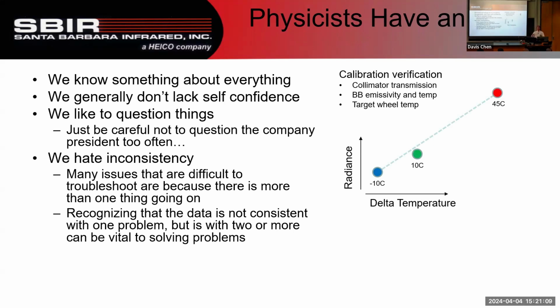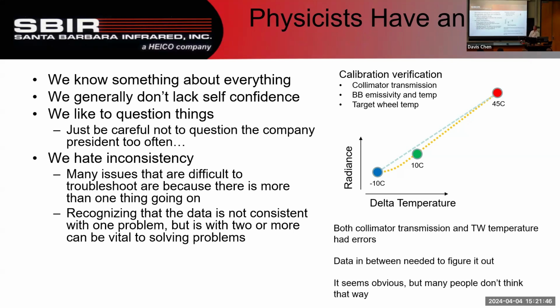And they come to me, nothing makes sense. I don't understand why. We run the test 5 or 10 times. Every time we run it, +10 fails. We don't understand why. So what do you ask? Well, what happens in between, right? Well, we don't know. Okay, go collect more data. I'm known for saying go collect more data. You won't believe it. People joke about me asking them to collect more data anytime they come to me to solve a problem. So they go and collect more data, and this is the curve it follows. So what happens? There's 2 things wrong. Number 1, the collimator transmission is wrong, and the target wheel temperature is wrong. And you can't tell that without having more data than just the 3 points.